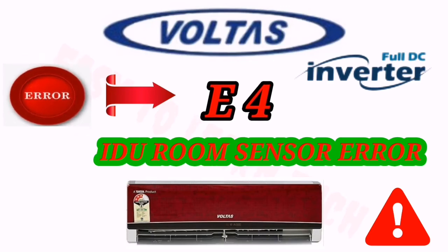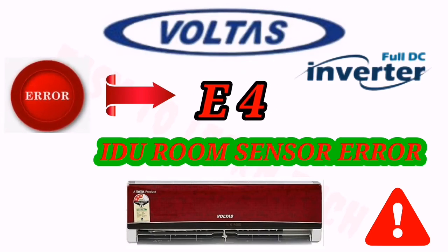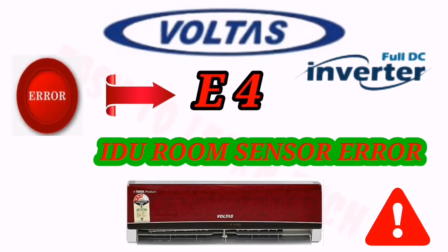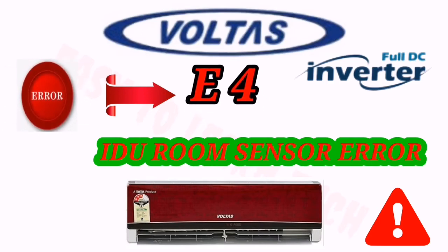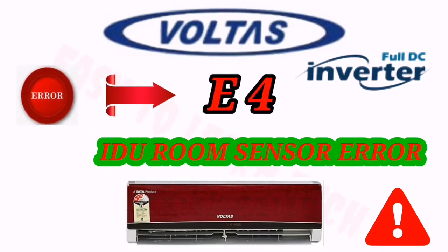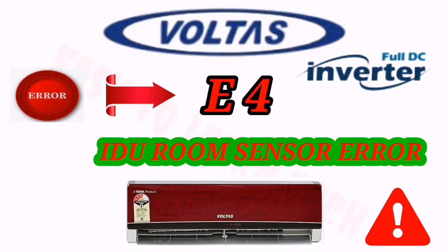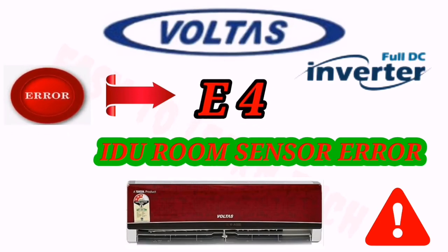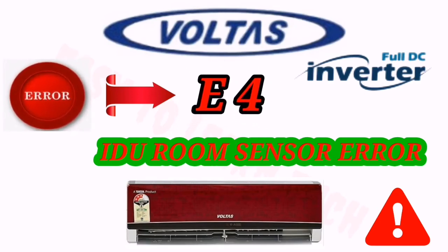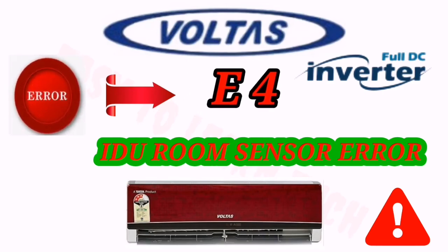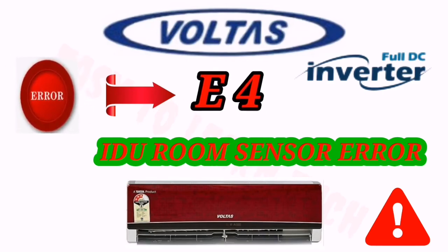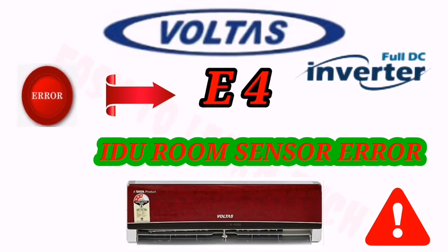And again, if you are getting the same error, then you have to disconnect the sensor and check the resistance of the sensor. The resistance should be 10 kilo ohms at 25 degrees Celsius. If it is less or more, then you have to change the sensor. And then you have to check the PCB output supply for the sensor. If the output supply from the PCB is not good, then you have to replace the indoor PCB. Our unit will be in working condition.